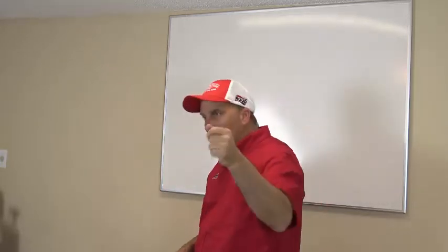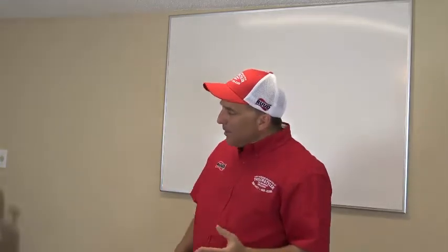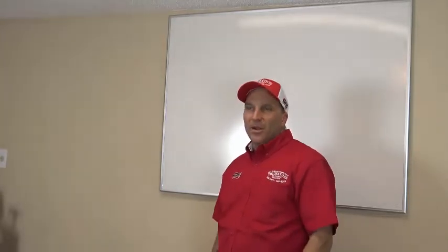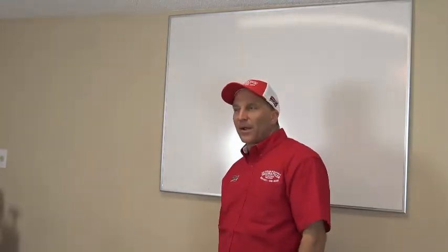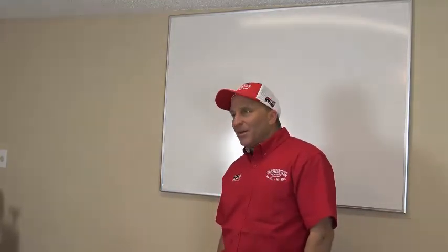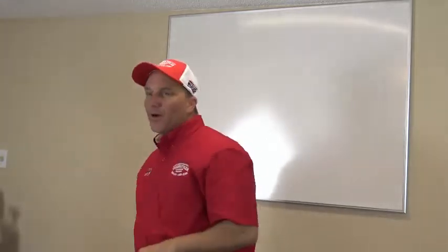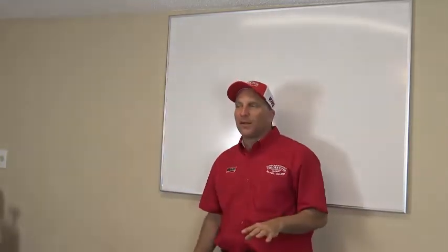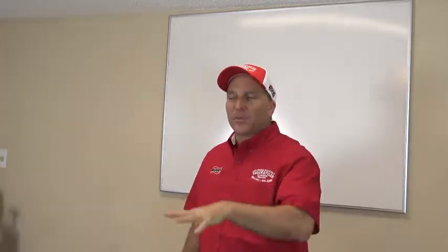And then when I went to go put it back on, I heard the noise, and I went, no, I don't think that's it. Well, but it was just bugging me, and I went inside, talked to the customer for a minute, then walked back out to my truck, got in my truck, went to go leave, and I'm like, let me go check. It's just bugging me. Got back out of my truck, went back there to the unit, put my hand over the condenser, it's blowing out cool air. Compressor's running though. Pull the plug on it, let it sit for 3 or 4 or 5 minutes, put it back in, boom, compressor sounded perfect again, started blowing hot air out again.